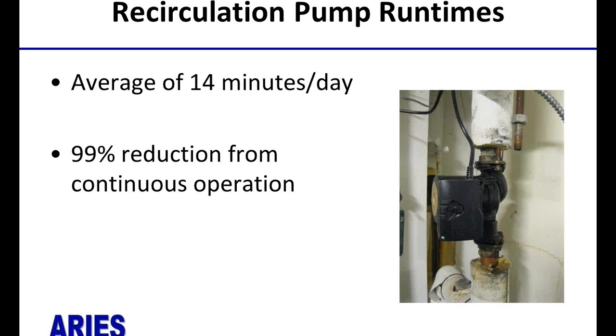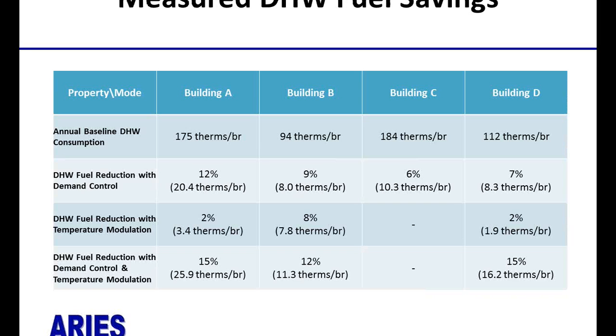So the recirculation pump runtime with demand control was reduced substantially and consistently. This is a good thing. The pump control had the pump running 15 minutes a day. That saved several thousand kilowatt hours a year, even with a fractional horsepower pump. And at local energy prices, that's something several $100s a year.